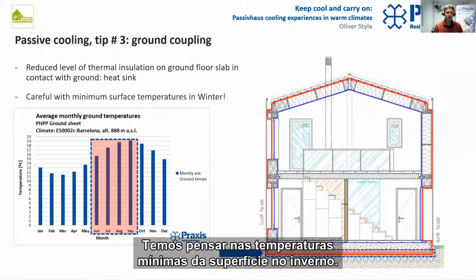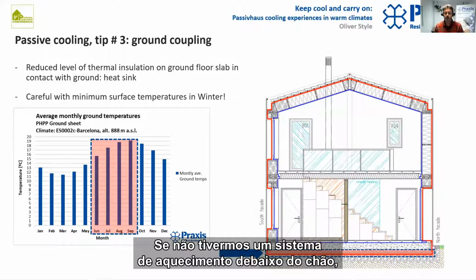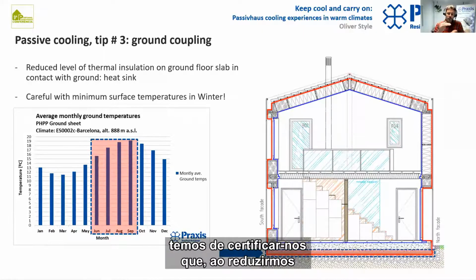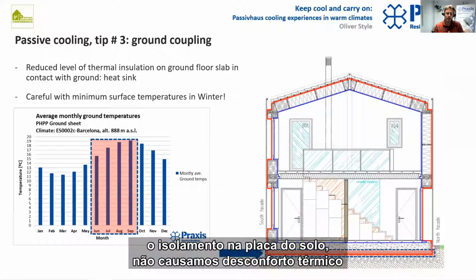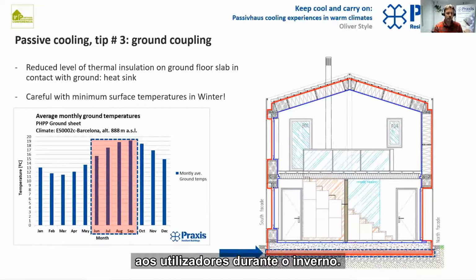We also need to just be careful of minimum surface temperatures in the winter. If we don't have an underfloor heating system, we need to make sure that if we reduce that amount of insulation on the ground floor slab, we're not going to cause thermal discomfort to users during the winter months.